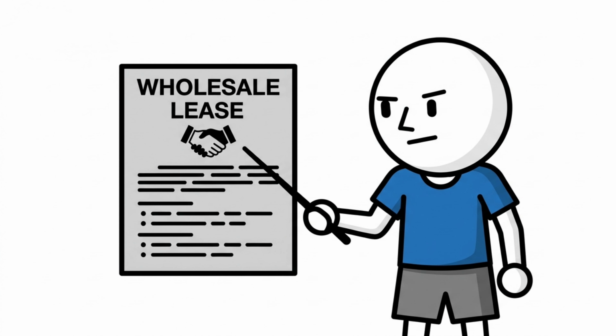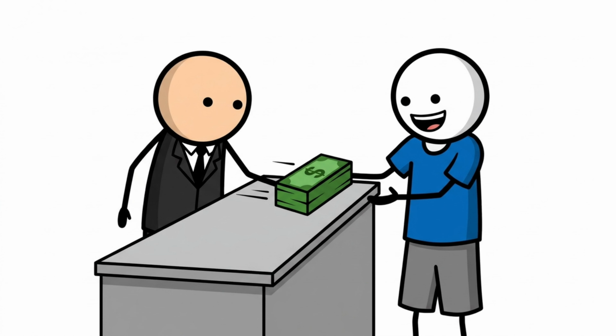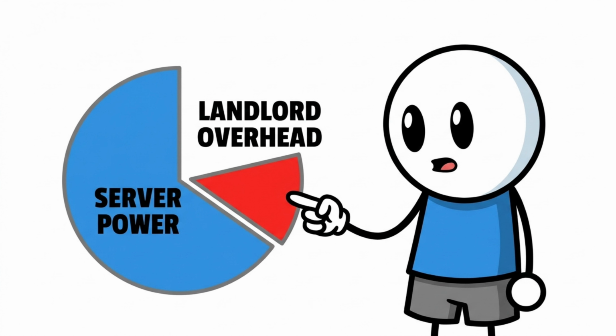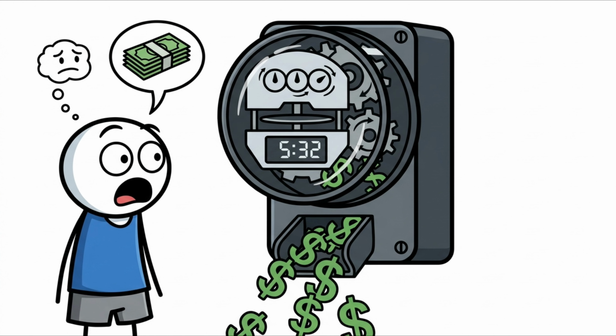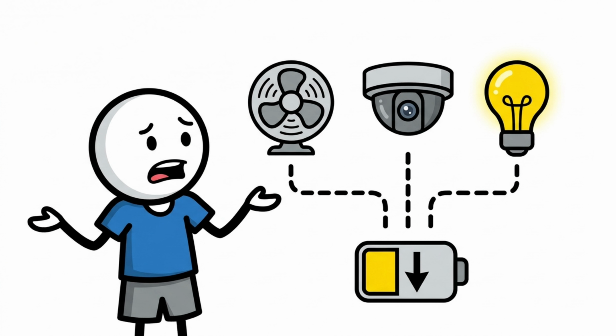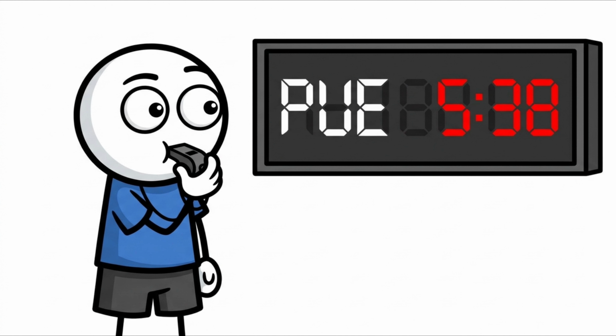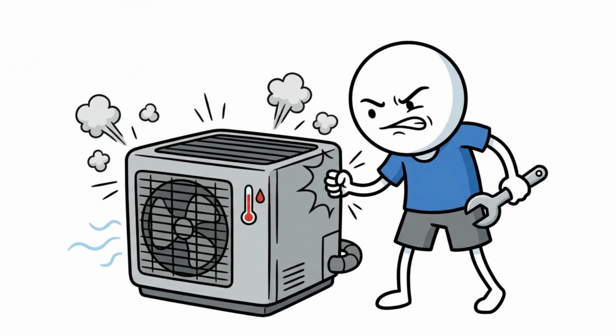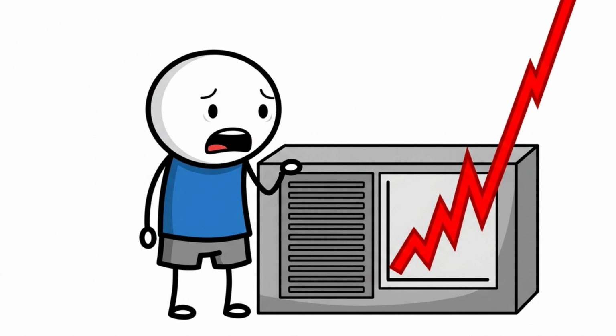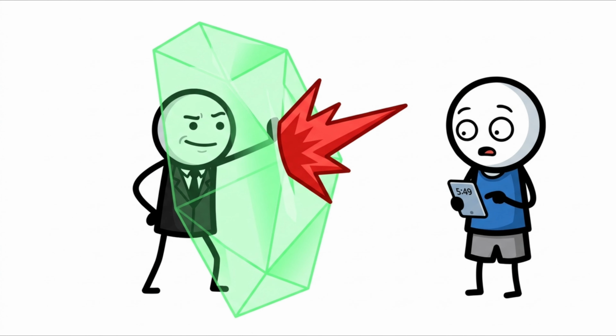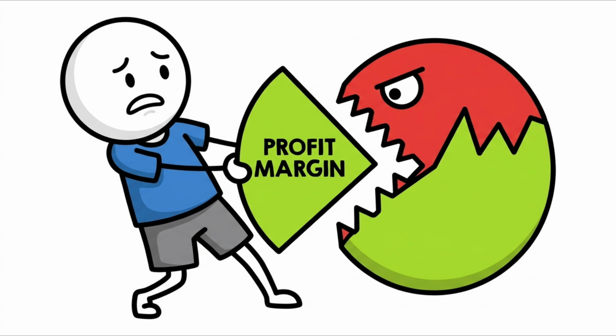In most wholesale leases, the tenant pays for the actual power their servers consume, but the landlord pays for the overhead. You pay the energy cost to run the chillers, the fans, the security systems, and the lighting. This overhead is tracked by a metric called power usage effectiveness. If your cooling system is old or inefficient, your overhead costs spike. The tenant does not absorb that inefficiency. You do. It comes straight out of your margin.